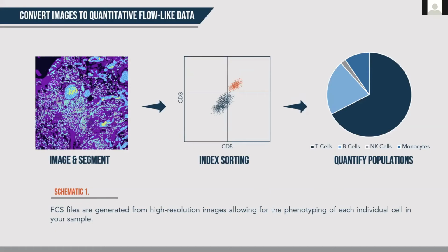So the way ChipCytometry works, looking at a 30,000-foot view, as I said, it's an image-based platform. You stain the sample with antibodies. The instrument takes a series of images and draws a border around every individual cell in the sample, and then measures the fluorescence intensity within those defined borders. And from that, it generates a quantitative data set of those fluorescence intensity values for every individual cell. Looking at each individual marker in the assay, it produces a data set we're all very familiar with, similar to what we see in flow cytometry. And from there, you can do your gating and phenotype and subphenotype all the populations that you might be interested in for a particular assay.